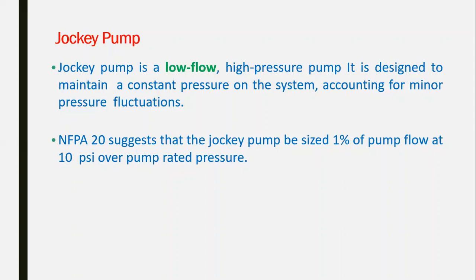And this one doesn't have a function during the firefighting operation. In case of fire, the jockey pump will not help anymore. It's a small pump having a low flow. Its function is only to overcome and maintain the pressure within the network at the rated pressure. If there is any leakage, any broken devices, any damage during testing or something, this jockey pump will operate once the pressure drops less than 5 psi from the rated pressure, or between 5 and 10 psi. The jockey pump will start operating to maintain it.